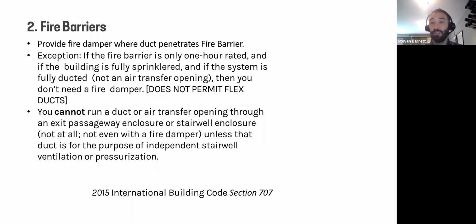Again, just like firewalls, this is going to seem like a theme here. Provide a fire damper when a duct or air transfer opening penetrates a fire barrier. But there is an exception, one that probably a lot of you know, and it goes like this. If the fire barrier is 1 hour rated, so it can't be 2 hours, 3 hours, max 1 hour, in a fully sprinklered building with a fully ducted system, so that rules out air transfer openings, then you can omit the fire damper. But key distinction, you cannot use flex ducts as part of your system.